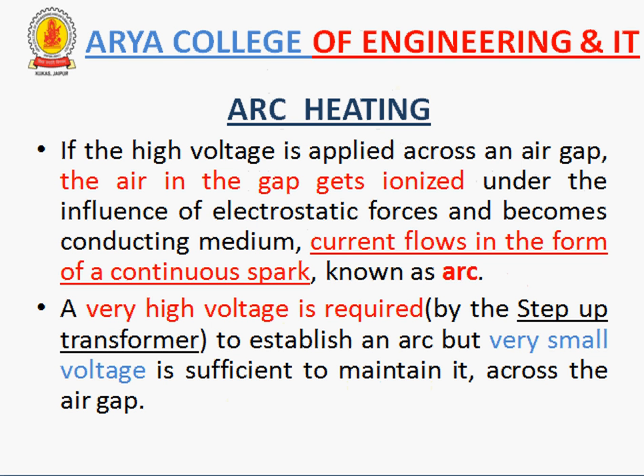Arc heating means current flows in the form of a continuous spark known as arc. If high voltage is applied across an air gap, the air in the gap gets ionized under the influence of electrostatic forces and becomes a conducting medium. Then current flows in the form of a continuous spark known as arc. These arcs require very high voltage to establish, but a very small voltage is sufficient to maintain the arc across the air gap. So high voltage is provided by the help of a step-up transformer.